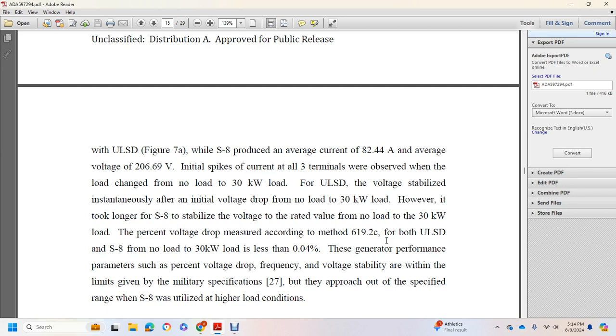An initial spike in the current of the three terminals was observed with the load change from no load to the 30 kilowatt load. The ultra-low sulfur diesel voltage stabilized instantaneously after the initial voltage dropped going from no load to 30 kilowatt load. However, the S8 took longer than the ultra-low sulfur to stabilize the voltage to the value it had at no load. The percent voltage drop, measured according to method 619.2C, for both the ultra-low sulfur and S8 from no load to 30 kilowatt load is less than 0.04% of the generator performance parameters. Performance, voltage drop, frequency, and voltage stability are within the limits of the military specification, but they approach the specified range.